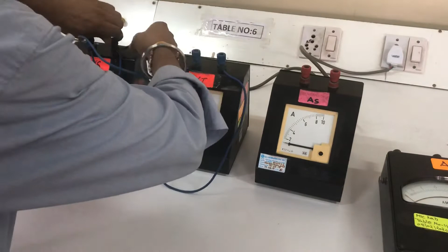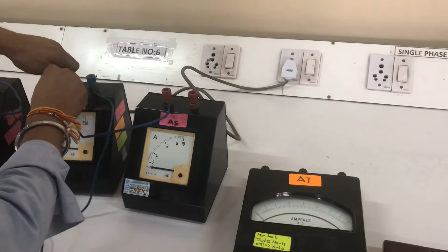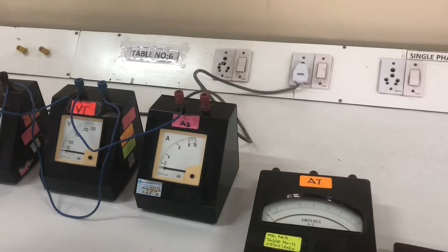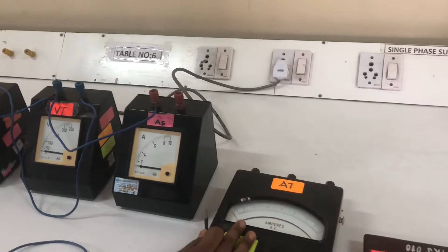Then from the test voltmeter we need to connect it to the standard ammeter, from the common of the test voltmeter to the common of the standard ammeter. The first terminal we consider as common and the second terminal we consider as range.